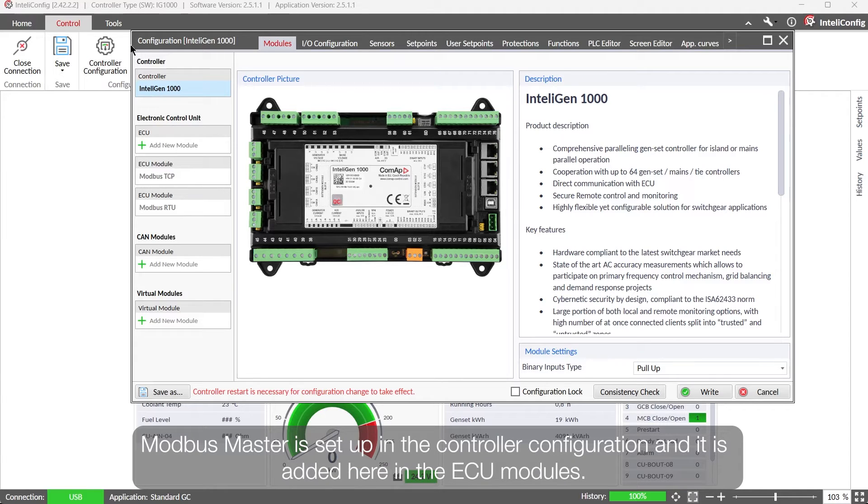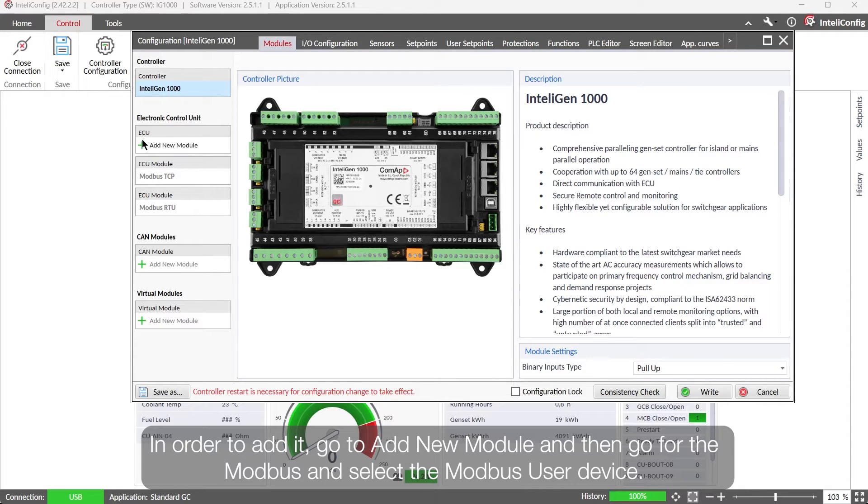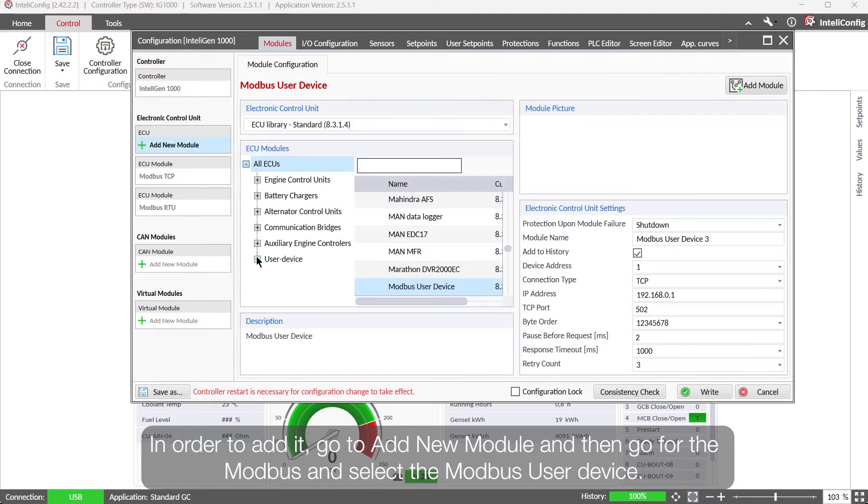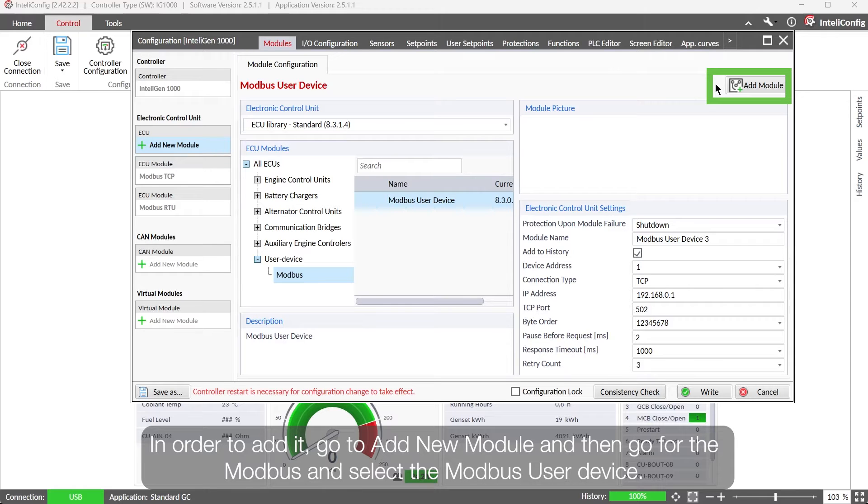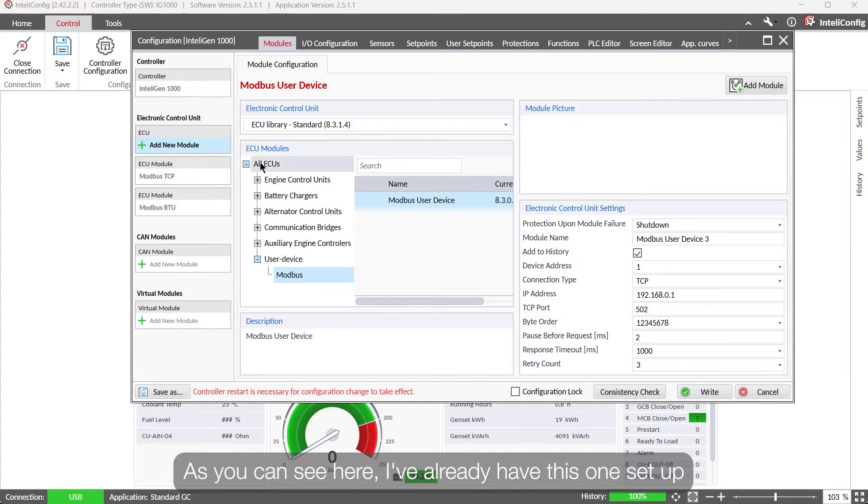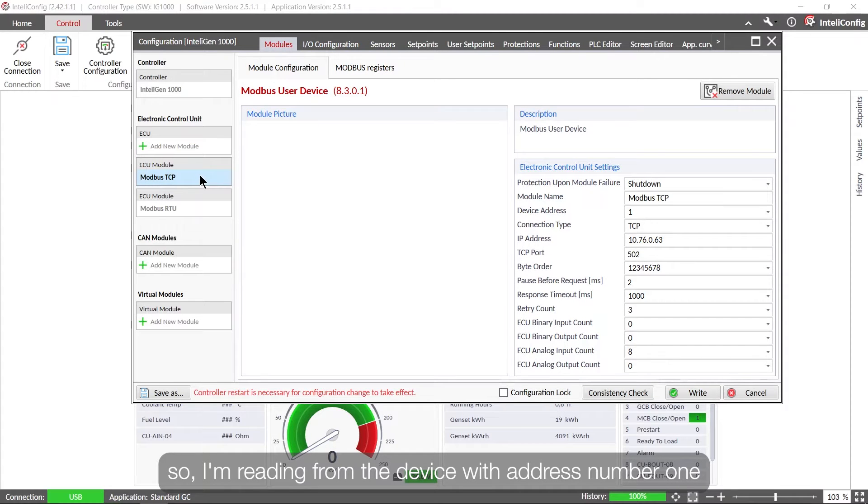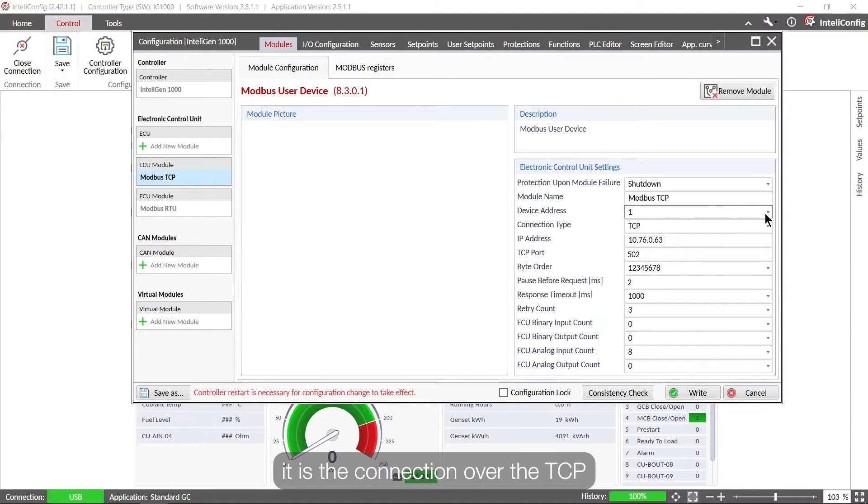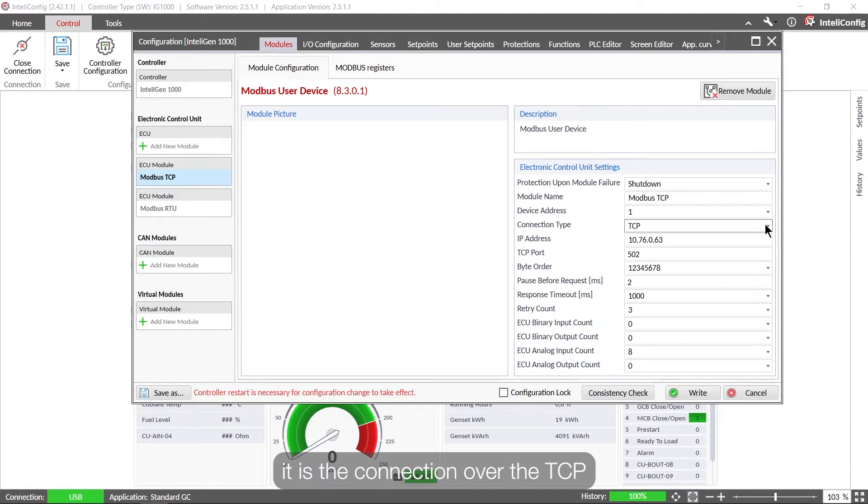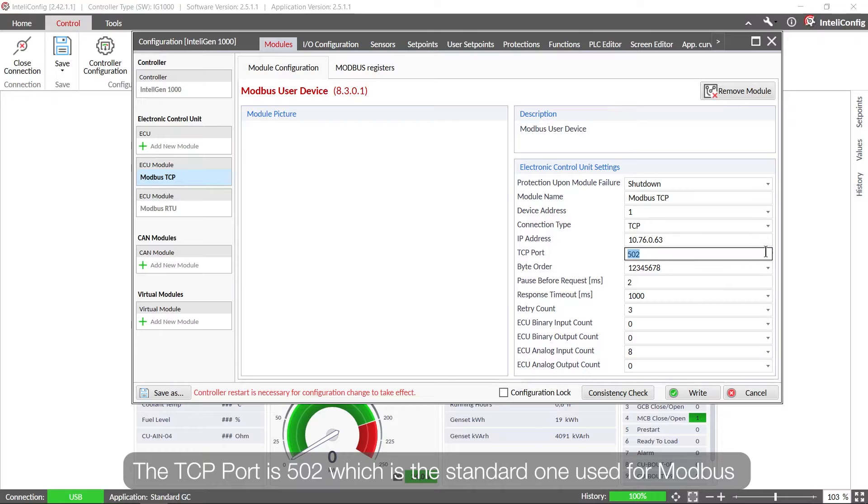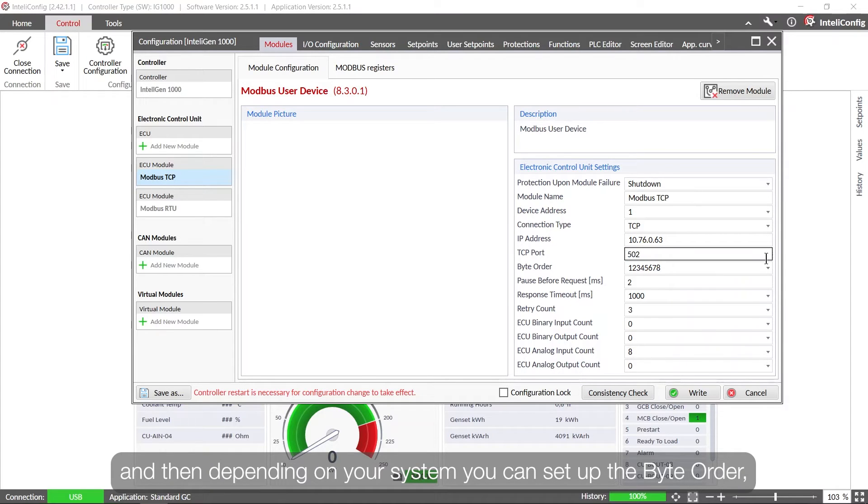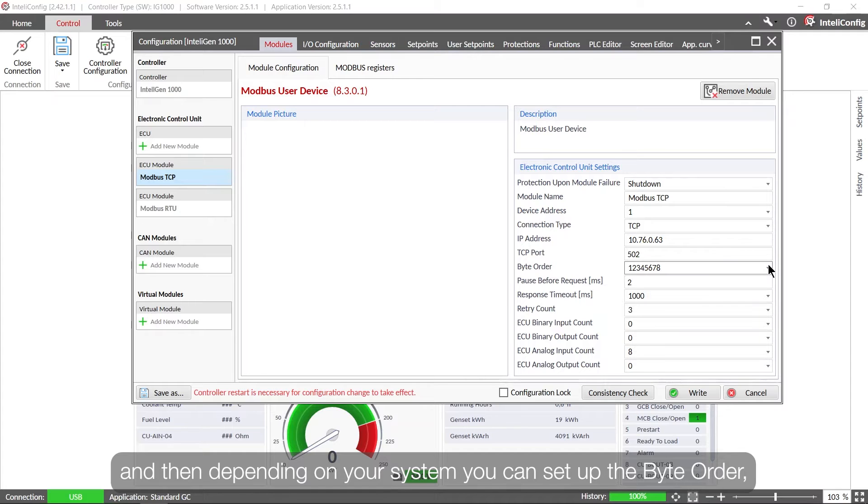Modbus master is set up in the controller configuration and it is added here in the ECU modules. In order to add it, go to add new module and then go for the Modbus and select the Modbus user device. So as you can see here I've already have this one set up, so I am reading from the device with address number one. It is the connection of a TCP from the IP address from this one. TCP port is 502 which is the standard one used for Modbus, and then depending on your system you can set up the byte order.